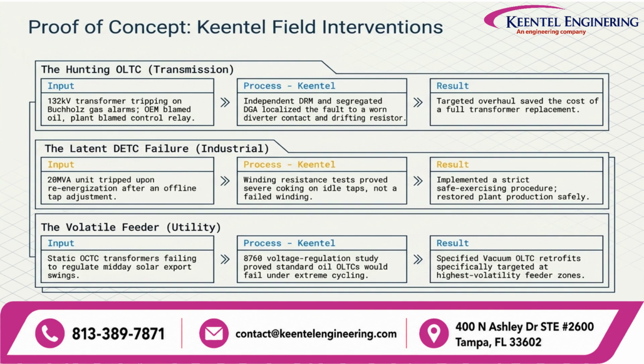In one transmission project, advanced testing identified deteriorating OLTC contacts before catastrophic failure occurred, allowing planned maintenance instead of an emergency outage. An industrial application revealed abnormal resistance signatures that led engineers to replace worn switching components, restoring reliable voltage regulation. In a utility feeder application, condition monitoring reduced unnecessary maintenance while improving transformer reliability. These examples illustrate the value of combining engineering expertise with modern diagnostic technology.